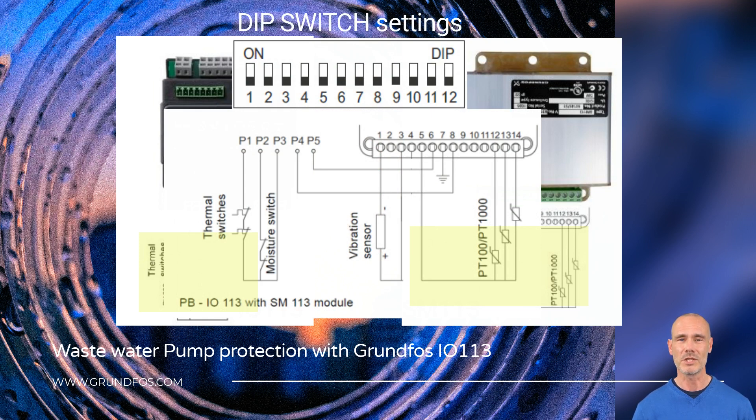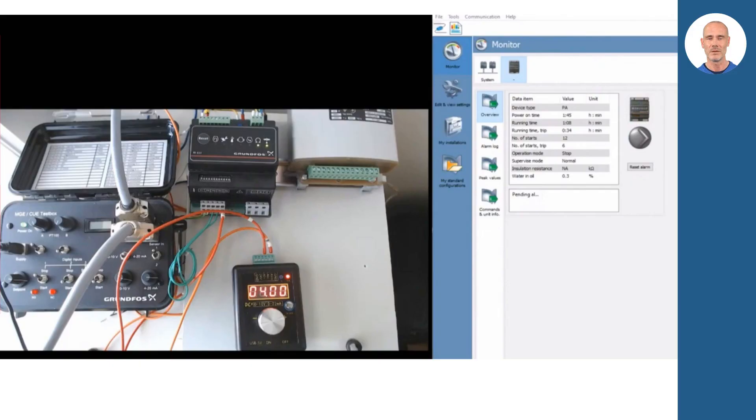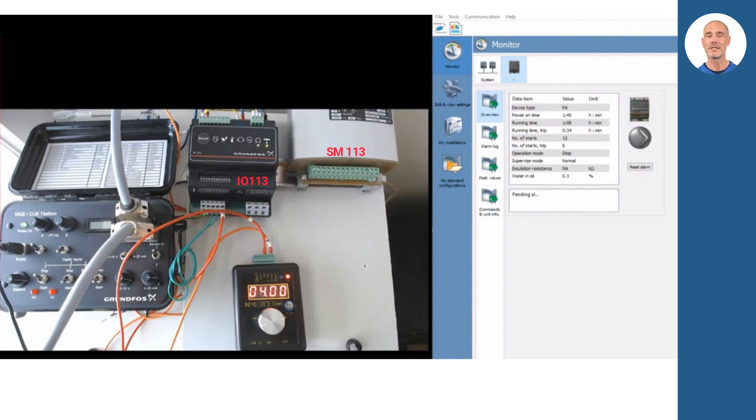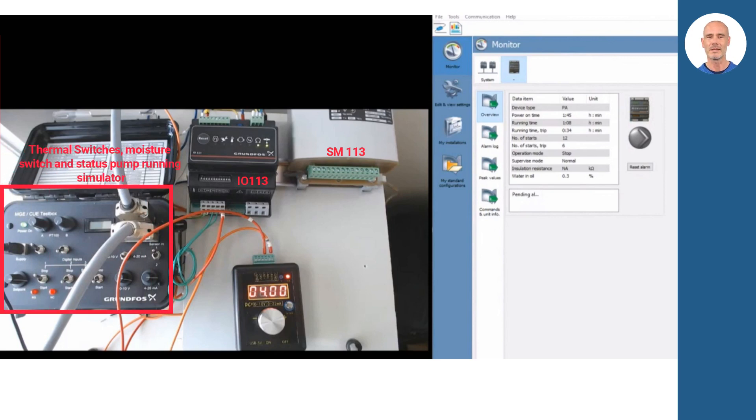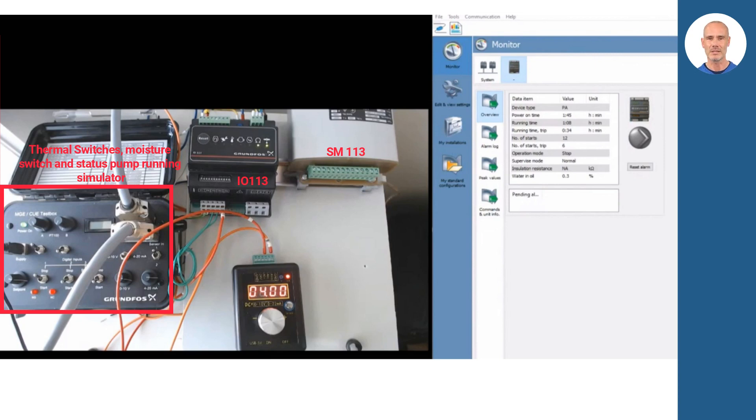Now we will show you some examples of functionality in simulations. We are going to start explaining the system simulation board. On the screen on your left, you will find a simulation board with signal simulation boxes, also with the Grundfos IO-113 pump protection unit and the module SM-113. With the signal simulator boxes, we reproduce the effect in the Grundfos module when different inputs change their status during pump operation. Those digital signals are thermal and moisture switches. We will also simulate the pump running status, connected in the K2 and K1.